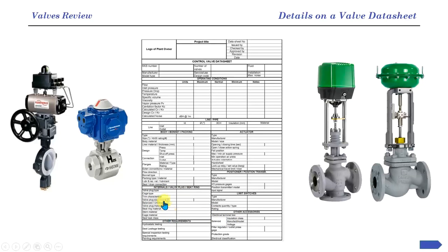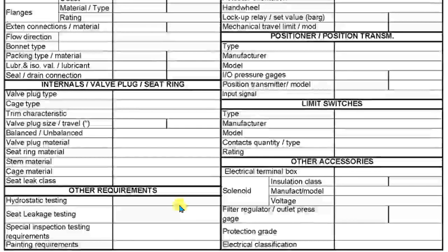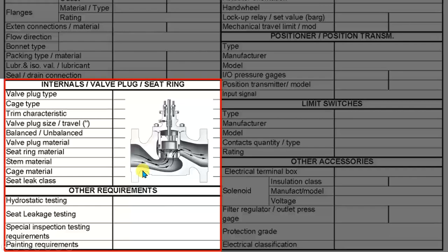The internal parts are the most important sections which need utmost expertise. Talking about the trim depends on the valve type. If you are talking about a globe control valve, the plug type and cage should be specified based on the application. Not only can these two determine the control characteristics of the valve, but they are also the main factors to handle cavitation and high pressure drop conditions. Multi-stage, multi-hole cage, and labyrinth trim are a few methods to eliminate cavitation. There are some options with other valve types with similar concepts, yet totally different designs.